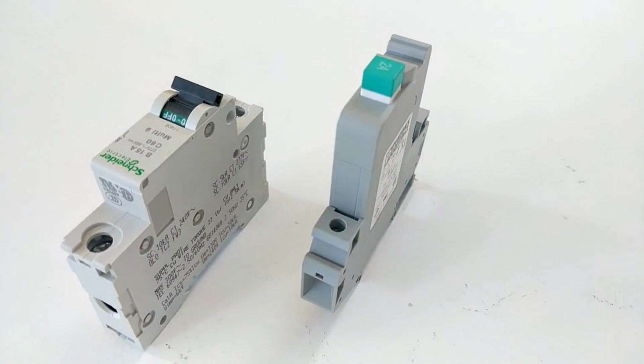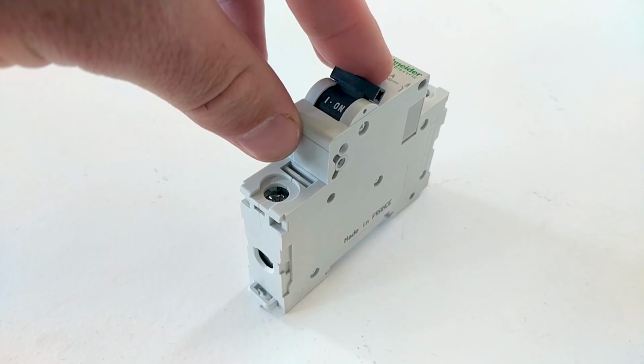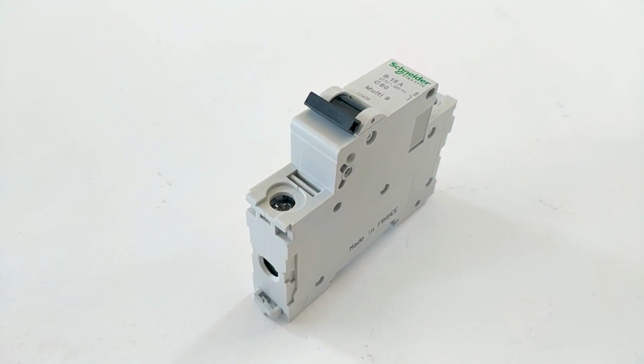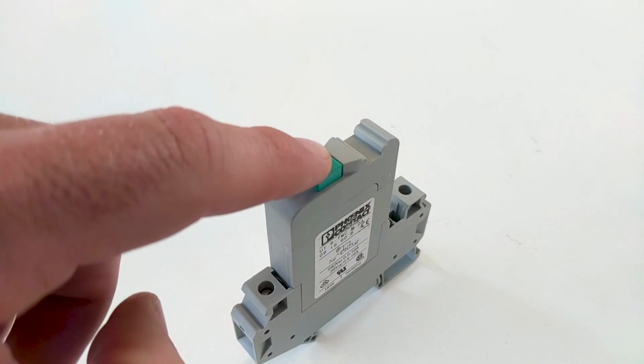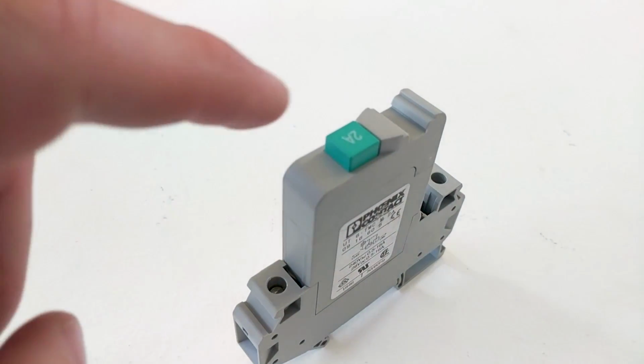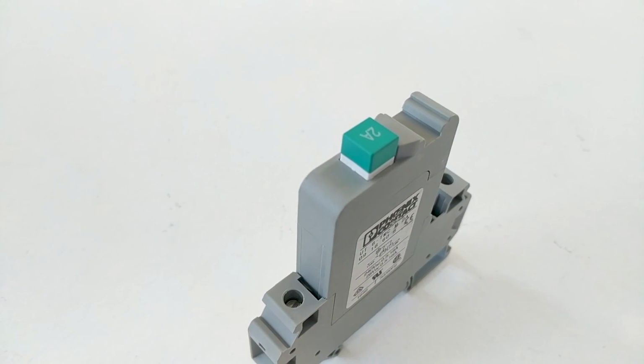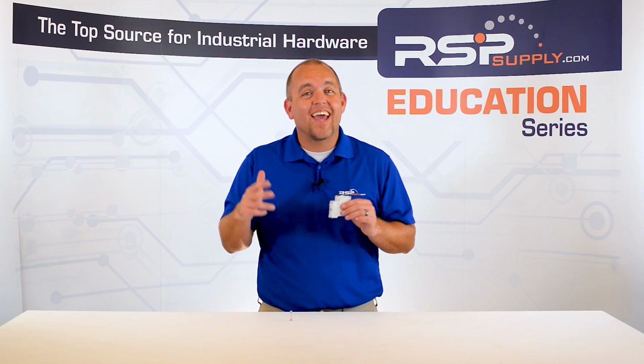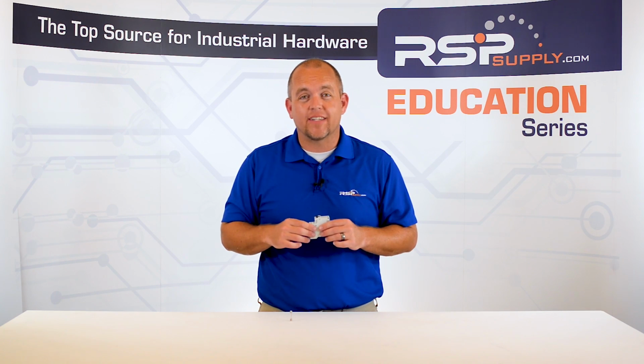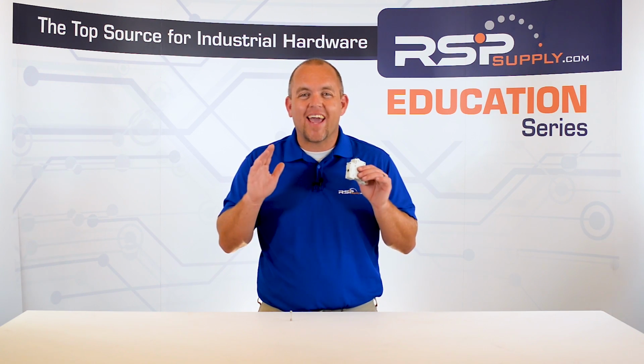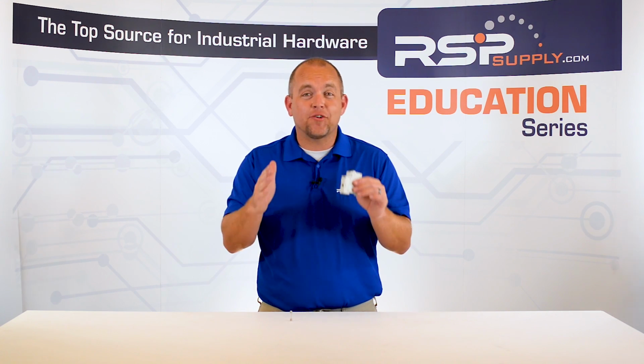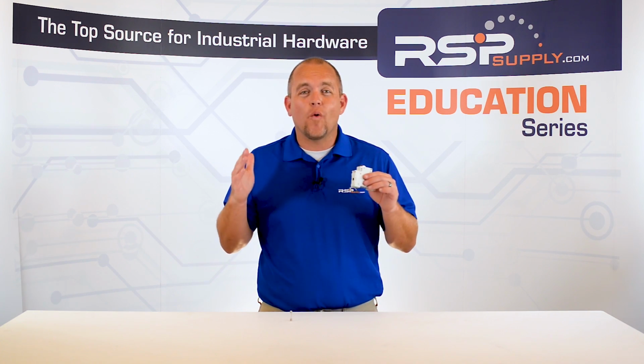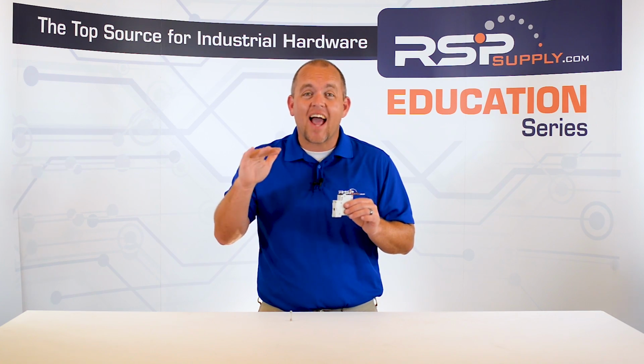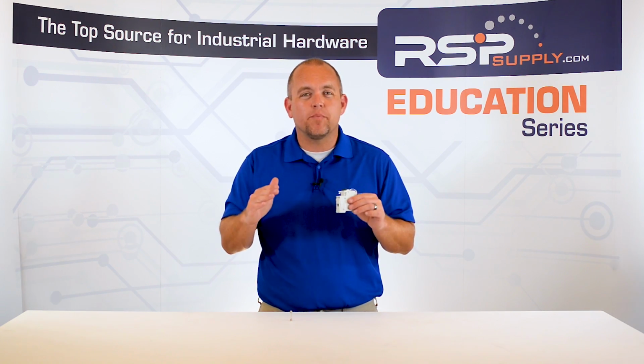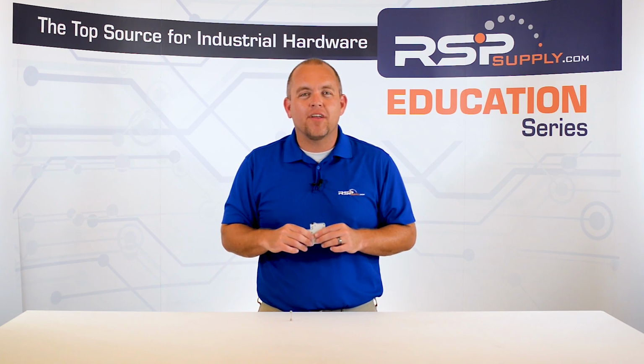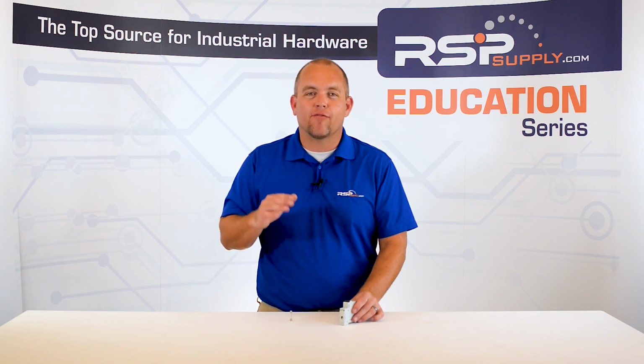Unlike fuses, circuit breakers are intended to be reused each time they are tripped by a power surge or overcurrent event. Much like fuses, circuit breakers are designed to trip at a certain current level. This is intended to protect both equipment and anyone in the area of that particular circuit. Circuit breakers can be found in just about any variation you can imagine, from a single phase, low current application, all the way to three phase and incredibly high current applications. This reusability and the amount of variations that can be found make them a great option in many different applications.